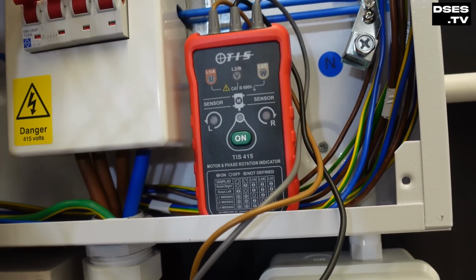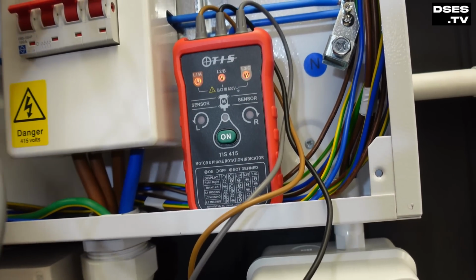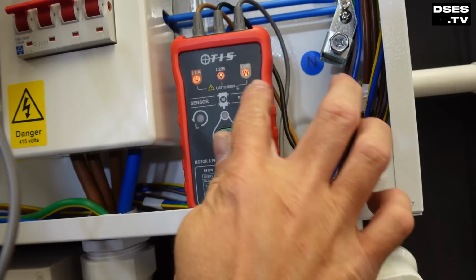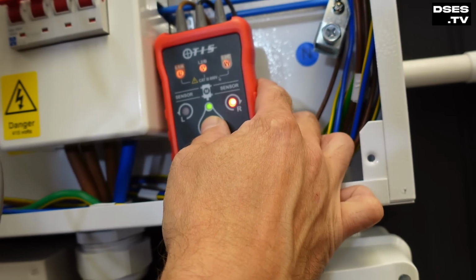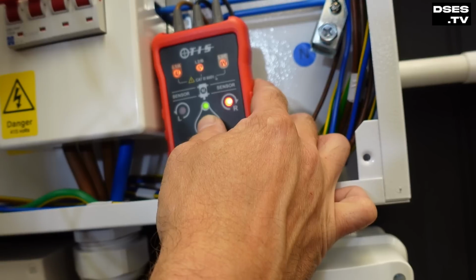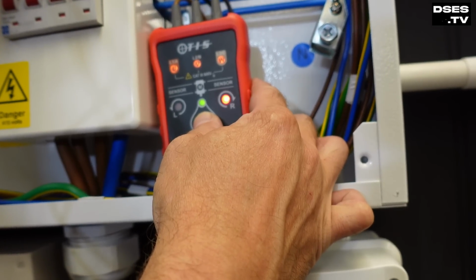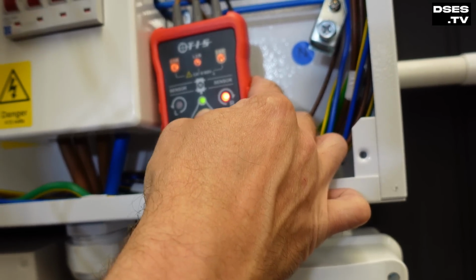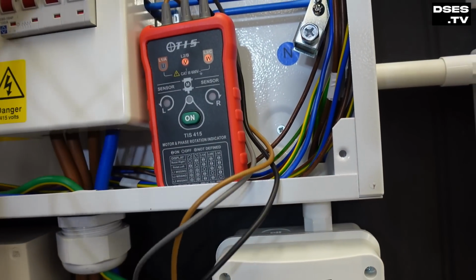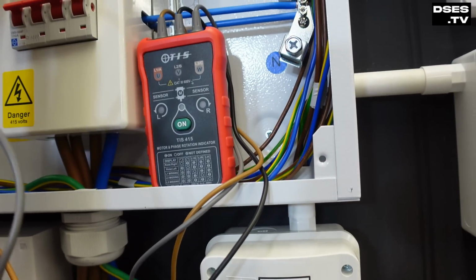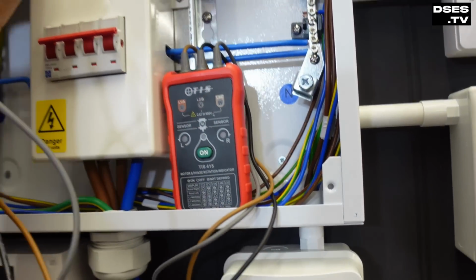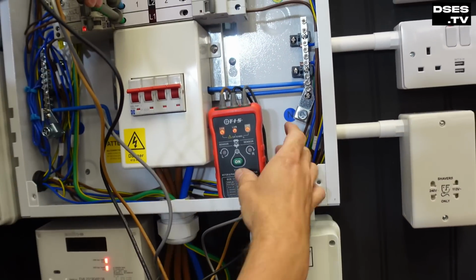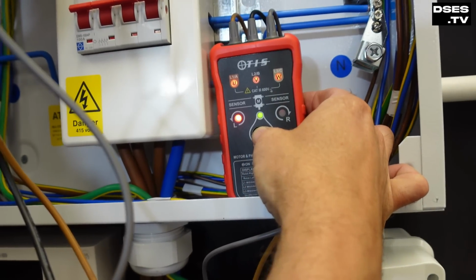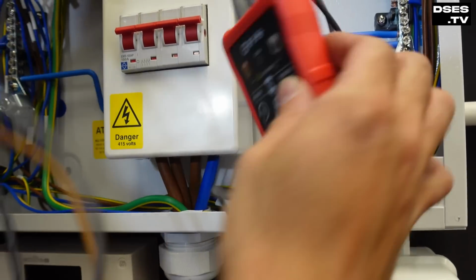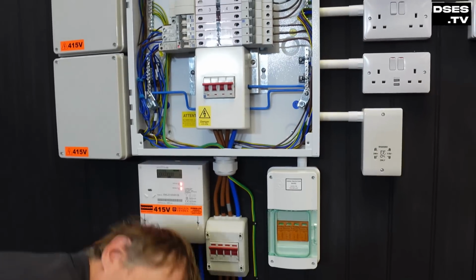If I can get those probes, the GS38 ends - again, we've got a light that lights up to say the voltage is okay per phase, and if I push this in, it's showing us that the phase rotation is correct. We are going clockwise. Again, if I were to reverse the phases as though they were being delivered wrong, or if we'd wired it up wrong, what we should see now is an anti-clockwise light, which is not what we want. Perfect. 2 down, 1 to go.